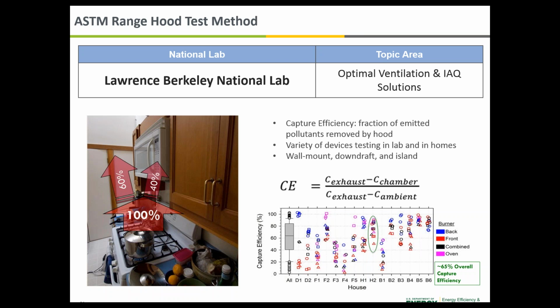Right now, range hoods are really only sold based on the fan flow and not so much the capture efficiency. So a consumer trying to get very good air quality in their kitchen might be drawn to a high CFM fan, but that may not actually deliver the improved IAQ performance. It may instead just increase the energy use and require more makeup air as a result of that higher CFM flow. You can see from the chart that the results are all over the map.